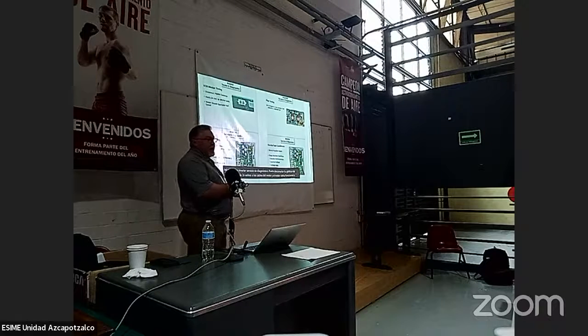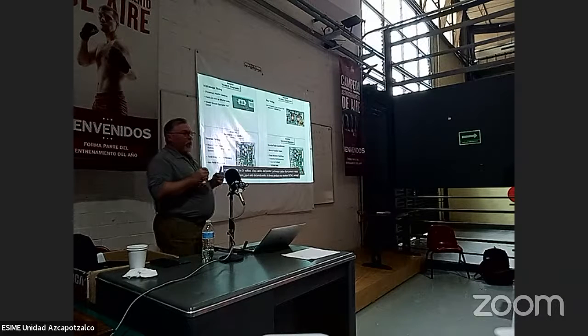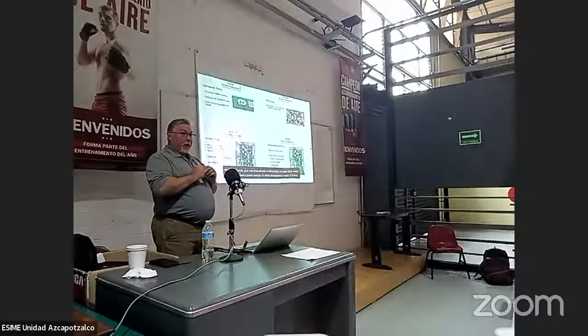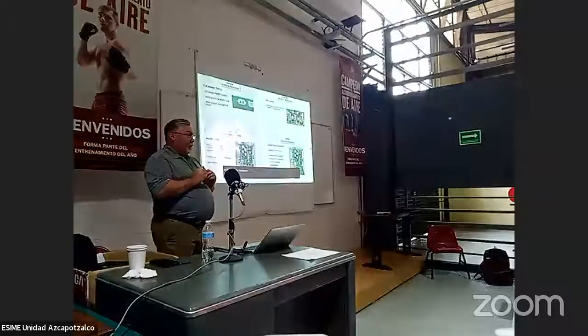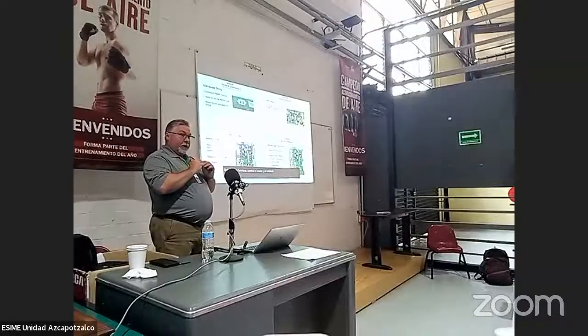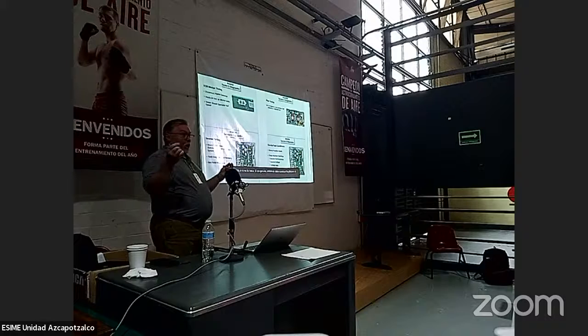Inverter service diagnostics: you can disconnect the PWM connector. By applying 24 volts to the motor leads, the motor should operate at full speed. So what this is saying is, if you want to test that ECM motor, you can unplug it and wire 24 volts straight to the motor. If the motor's good, it should run. If the motor doesn't run, change the motor or the module. If it does run, then you need to change the board or the cable going to it. Verify the cable is not open. Read both ends of the cable to make sure that they read normal before you change the board.